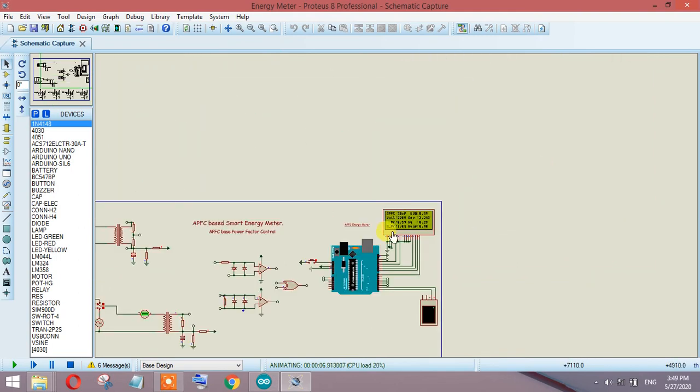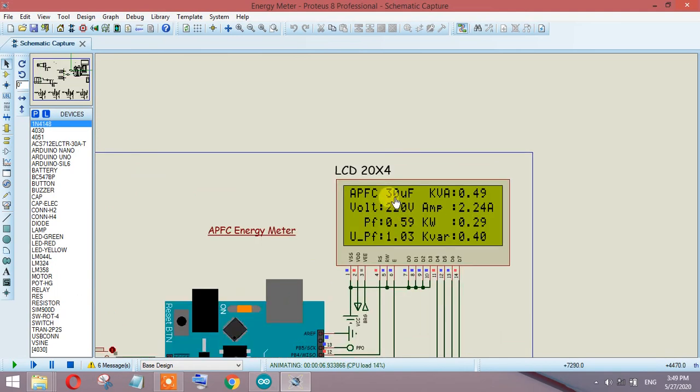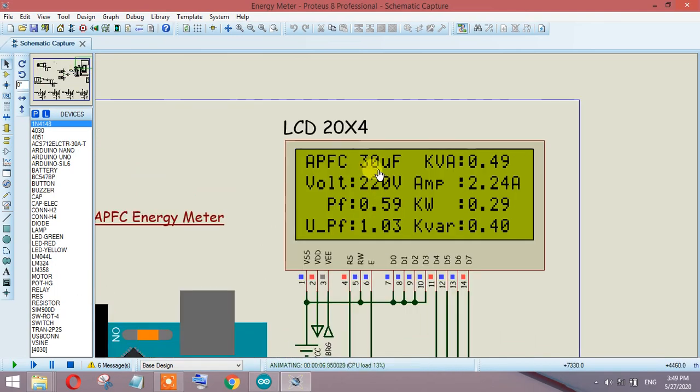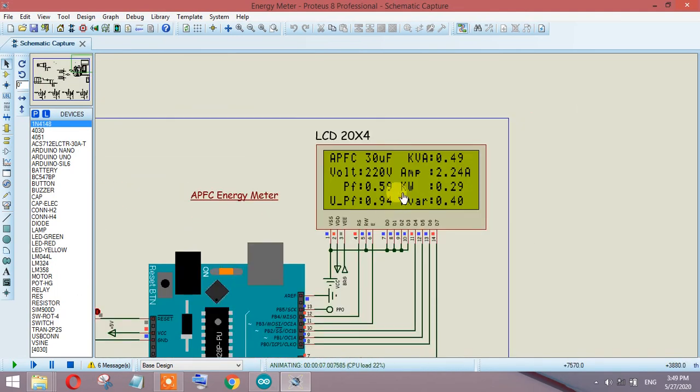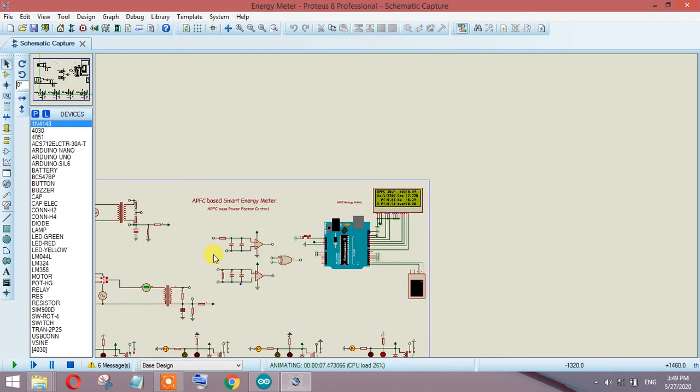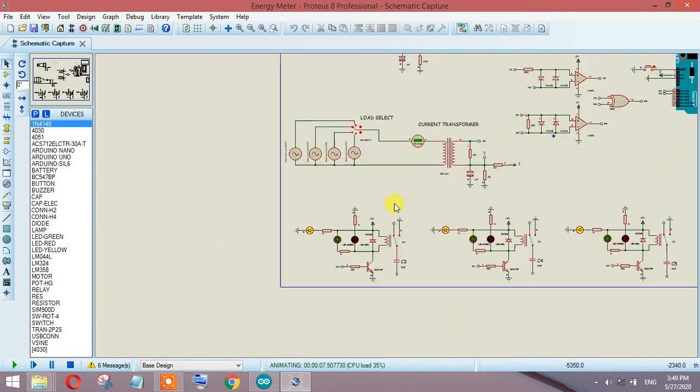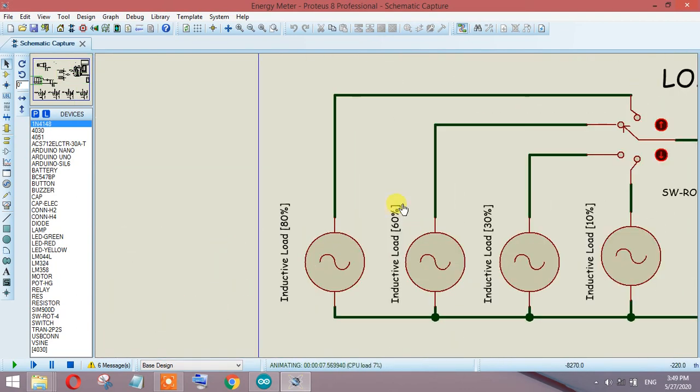Now the system is running on 30 microfarad and we are getting 0.59 as the actual power factor, updated to 0.94.